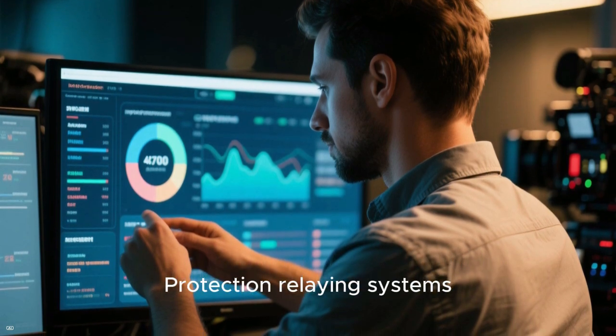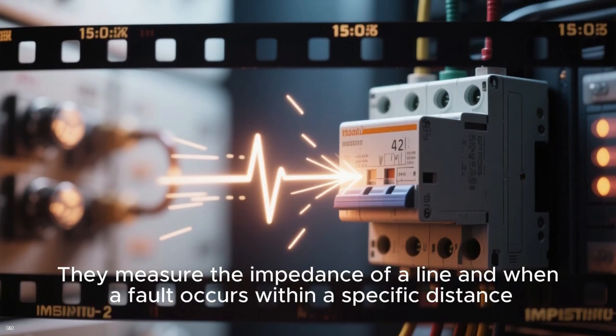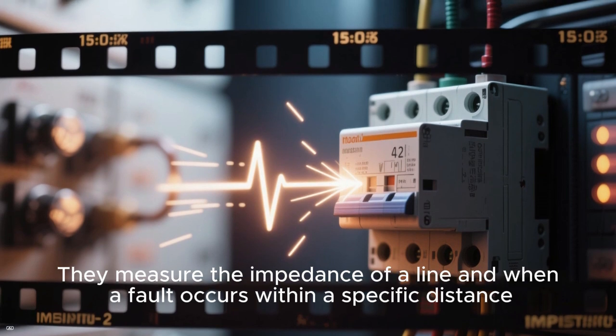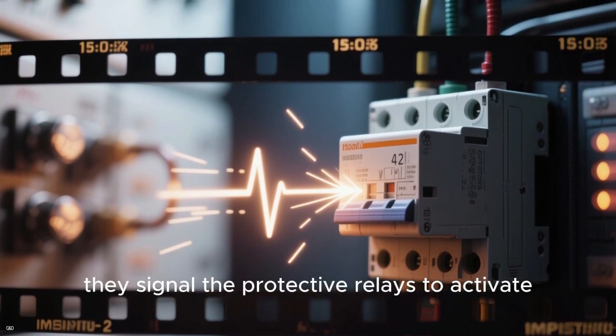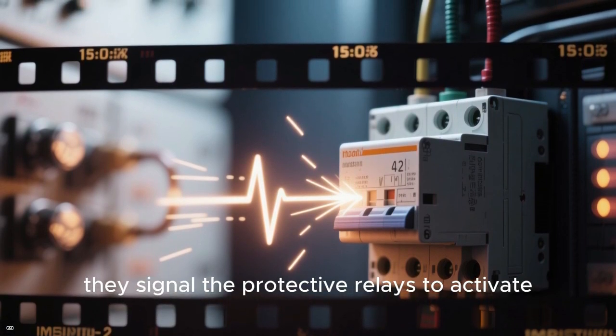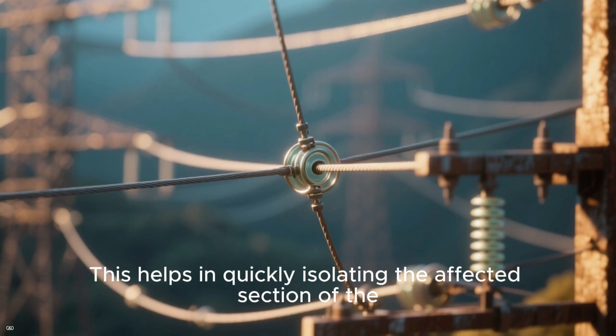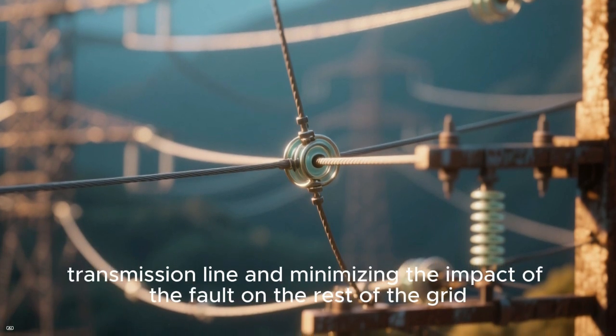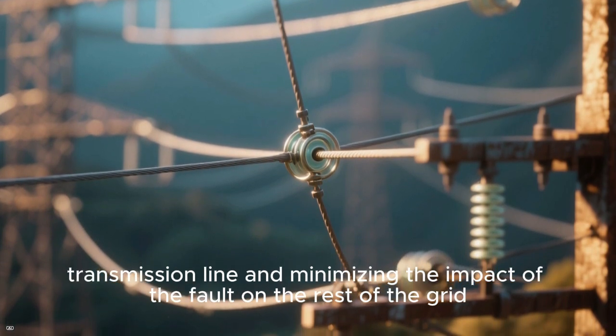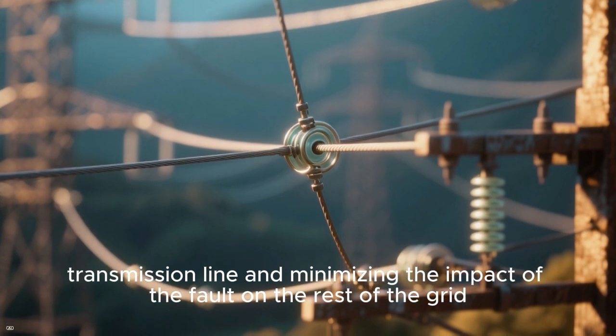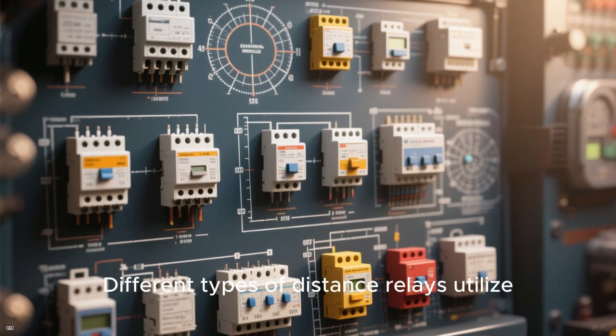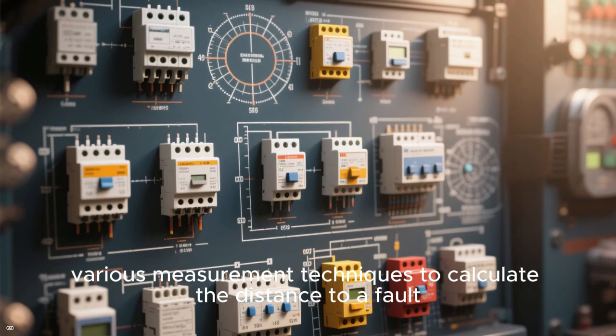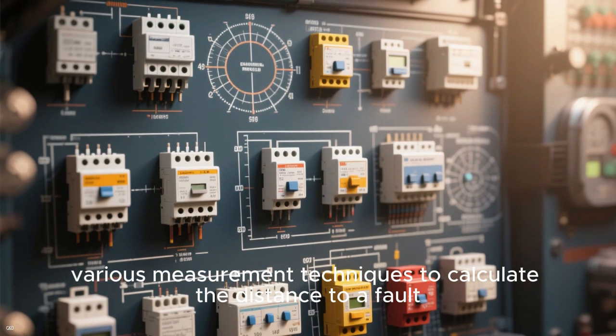They measure the impedance of a line, and when a fault occurs within a specific distance, they signal the protective relays to activate. This helps in quickly isolating the affected section of the transmission line and minimizing the impact of the fault on the rest of the grid. Different types of distance relays utilize various measurement techniques to calculate the distance to a fault.